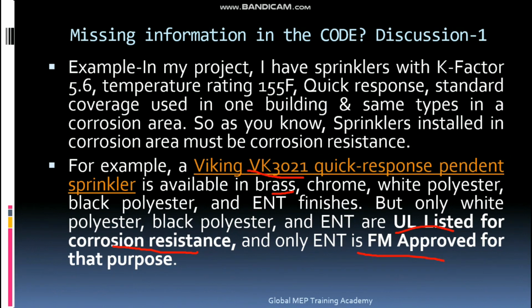You have to order a new one which has the corrosion resistant approval from Viking, and you have to close the zone control valve nearest to the affected area, and you have to wait until the suitable sprinkler comes for the installation.